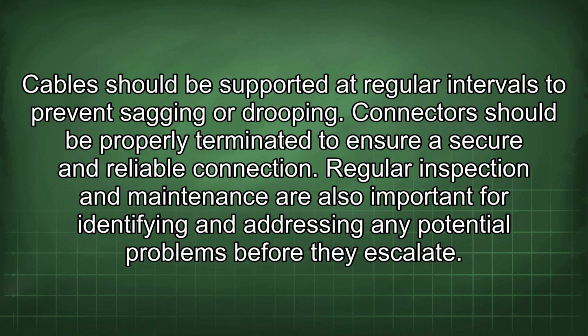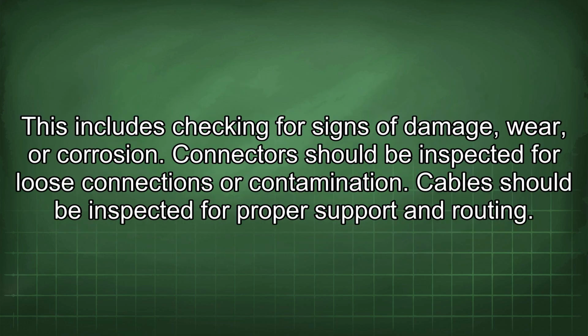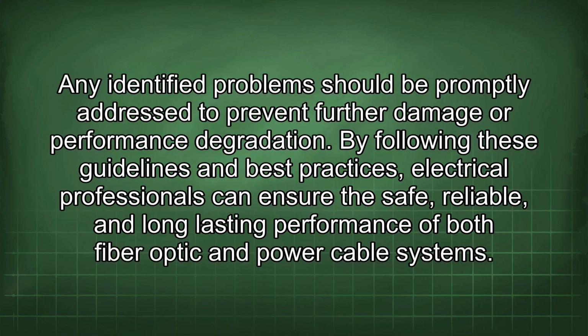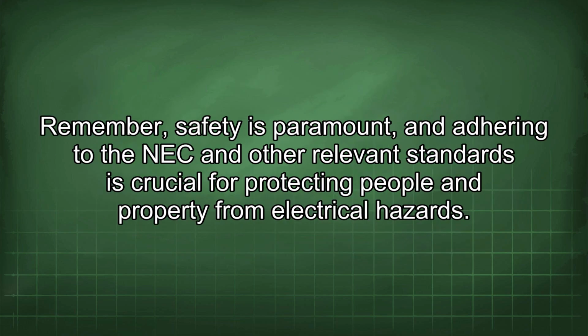Regular inspection and maintenance are also important for identifying and addressing any potential problems before they escalate. This includes checking for signs of damage, wear, or corrosion. Connectors should be inspected for loose connections or contamination. Cable should be inspected for proper support and routing. Any identified problems should be promptly addressed to prevent further damage or performance degradation. By following these guidelines and best practices, electrical professionals can ensure the safe, reliable, and long-lasting performance of both fiber optic and power cable systems. Remember, safety is paramount, and adhering to the NEC and other relevant standards is crucial for protecting people and property from electrical hazards.